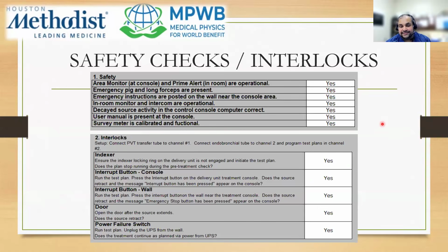Then you do your interlock test. You need to make sure that while the source is at a dwell position and you test out your interlock buttons, the source goes back to the safe in the afterloader. So you have your interrupt button, you have opening the door, and then you can turn your key, not to the off position, and then of course your main emergency button.